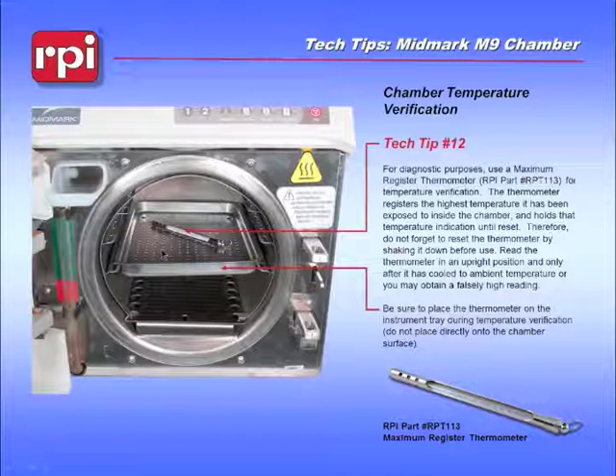test strips or spore strips or spore tests in the center of the chamber, as close to the center of the chamber as possible, on a tray. You never want to put them on the bottom of the tray rest or a tray assembly, and you wouldn't want to put them up in the top. They really need to be centered within the chamber.